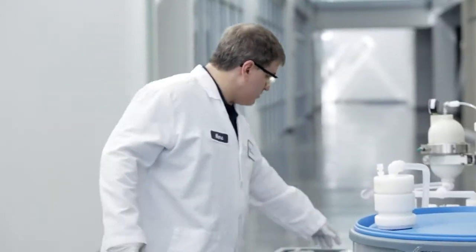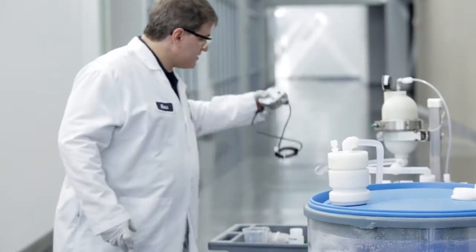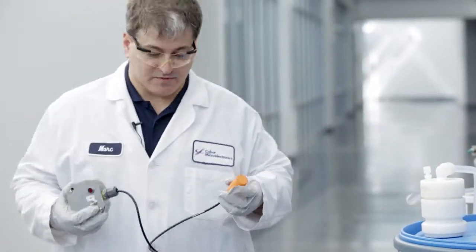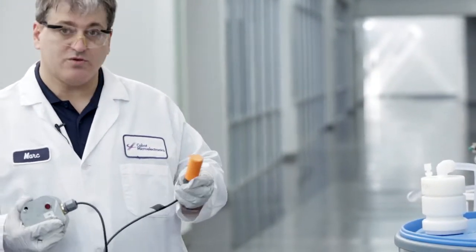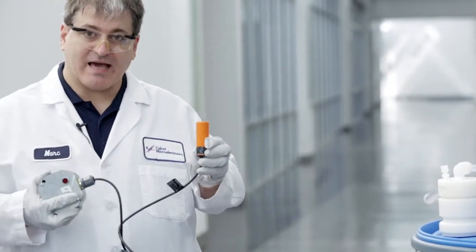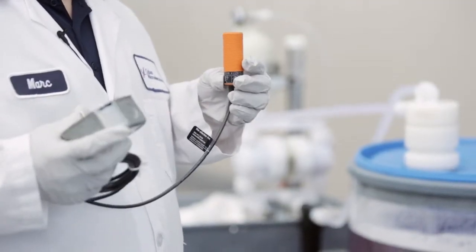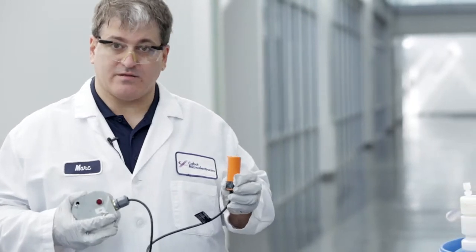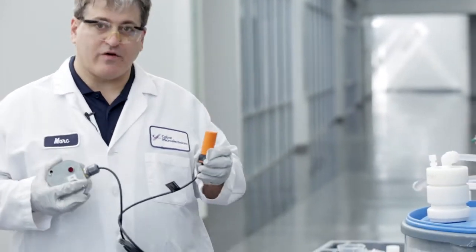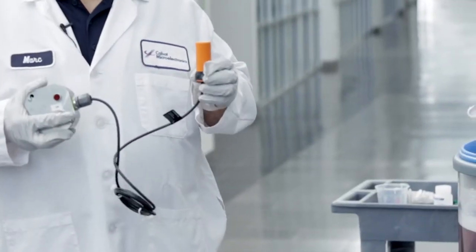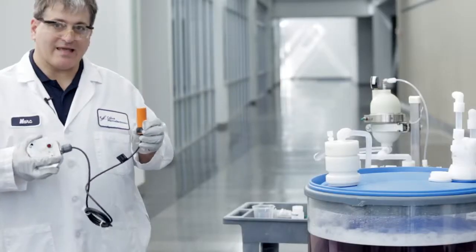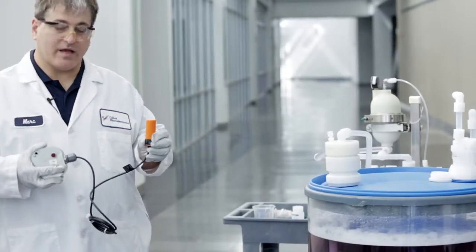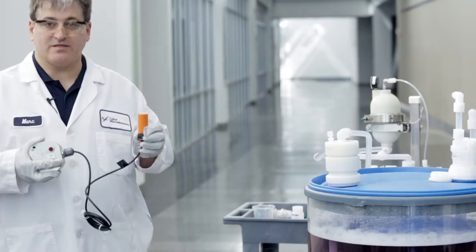The third reason that foam is a concern has to do with the design of distribution systems. Many distribution systems use capacitive sensors, which are non-contact level sensors, in order to determine the liquid level inside drums and tanks in the system. If you have foam present and it interacts with the capacitive sensor, you will not get an accurate reading on what your liquid level is inside a tank.